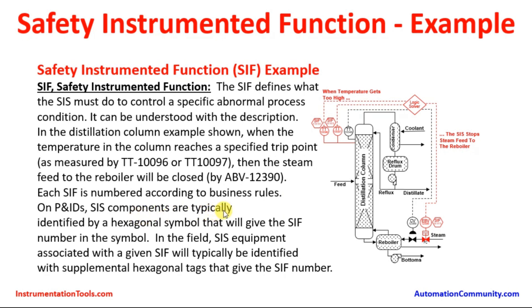On the P&ID, SIS components are typically identified by a hexagonal symbol that shows the SIF number. Seeing this SIF number in a hexagonal symbol is the identification for the safety instrumented function. These temperature elements belong to the safety instrumented system and carry a SIF number. Similarly, the emergency block valve also belongs to the SIS and carries the same SIF number. In a process plant, there are several thousands of sensors, valves, and other measurement elements, so each has to be identified separately.